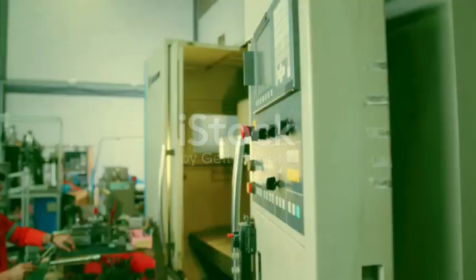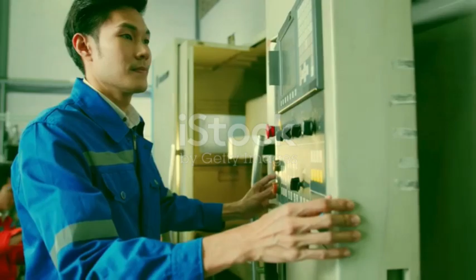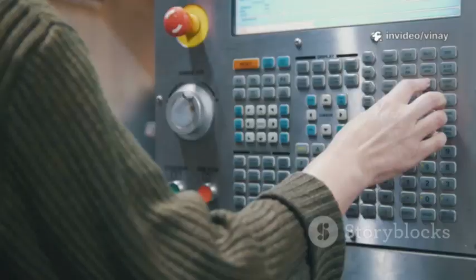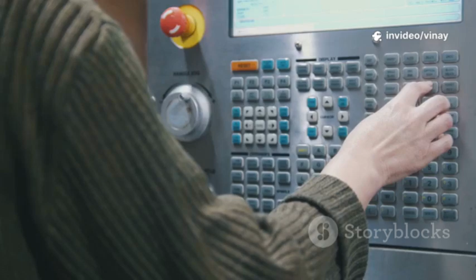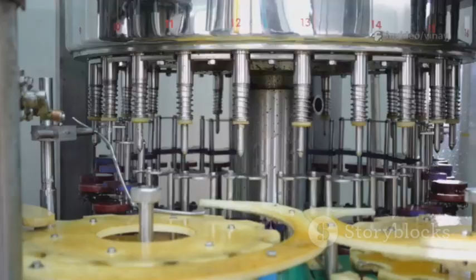With installation complete, operational qualification, or OQ, tests if the machine works as intended. Every function—buttons, sensors, alarms—is systematically tested against specifications. The OQ protocol lists all tests and acceptance criteria, like verifying temperature ranges or emergency stops.